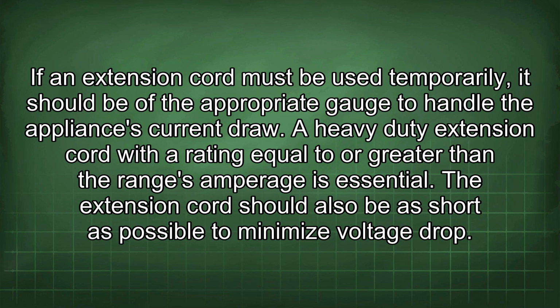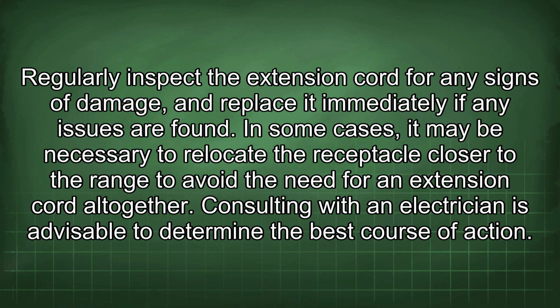The extension cord should also be as short as possible to minimize voltage drop. Regularly inspect the extension cord for any signs of damage and replace it immediately if any issues are found. In some cases, it may be necessary to relocate the receptacle closer to the range to avoid the need for an extension cord altogether. Consulting with an electrician is advisable to determine the best course of action.